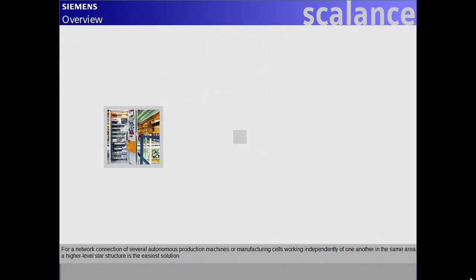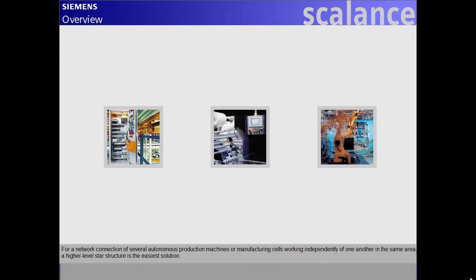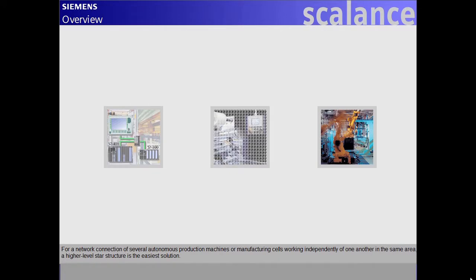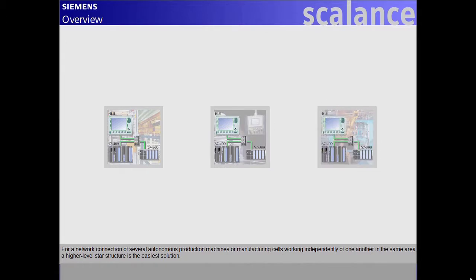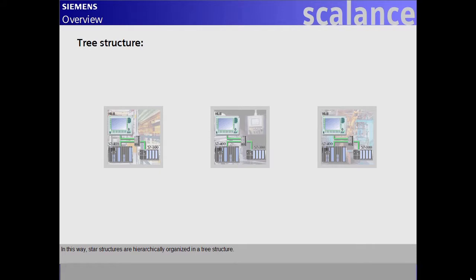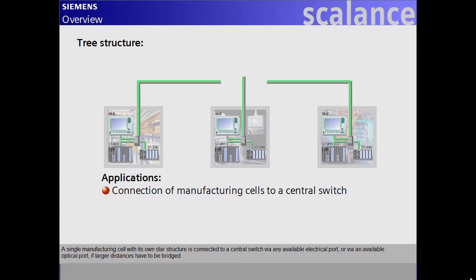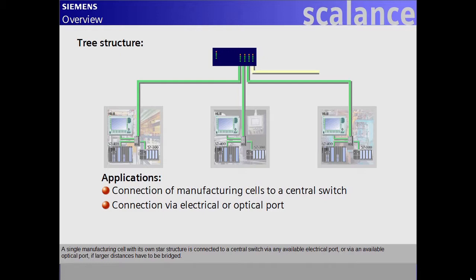For a network connection of several autonomous production machines or manufacturing cells working independently of one another in the same area, a higher level star structure is the easiest solution. In this way, star structures are hierarchically organized in a tree structure. A single manufacturing cell with its own star structure is connected to a central switch via any available electrical port, or via an available optical port if larger distances have to be bridged.